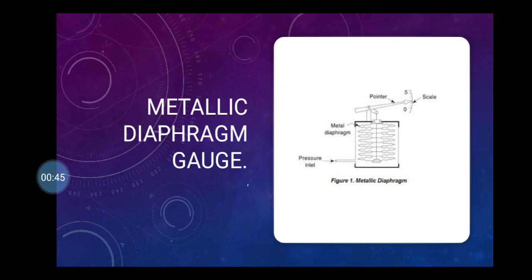There are different diaphragms: flat type, corrugated type and dished type. The selection of types depends upon strength and the amount of deflection desired. Generally there are two types of diaphragm gauge. The first one is the metallic diaphragm gauge and the other one is the slack diaphragm gauge. So let's study about the metallic diaphragm gauge.